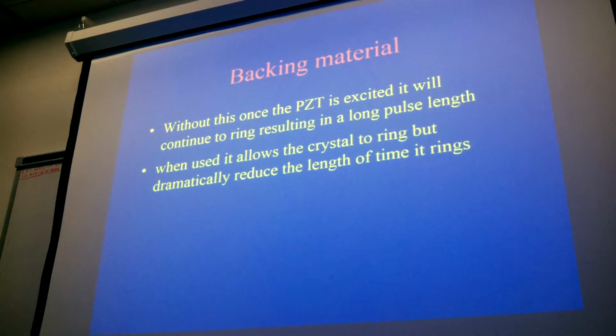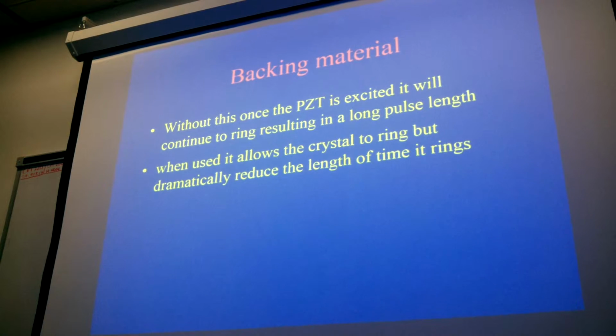Okay. It reduces the ringing dramatically, and it reduces the time. So instead of having 5 or 6 pulses, it'll have two or three or 2. It decreases the number of pulses in each transmission because it causes a thump. The only thing that doesn't is what? What continually rings? Continuous wave transducers. Because they're constantly sending and constantly receiving because they have 2 crystals. Like therapeutic ultrasound. Yes, but that's only sending. Therapeutic just sends.